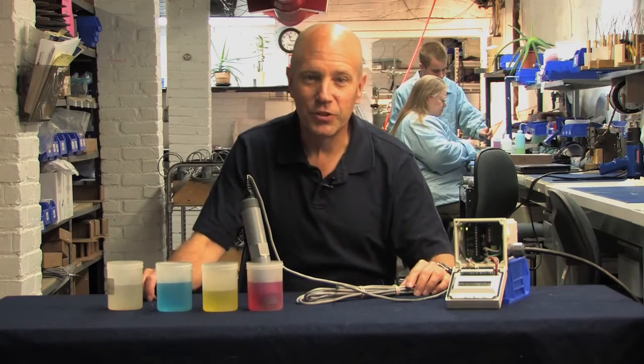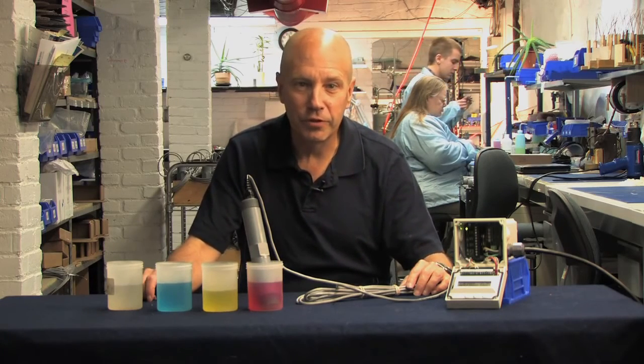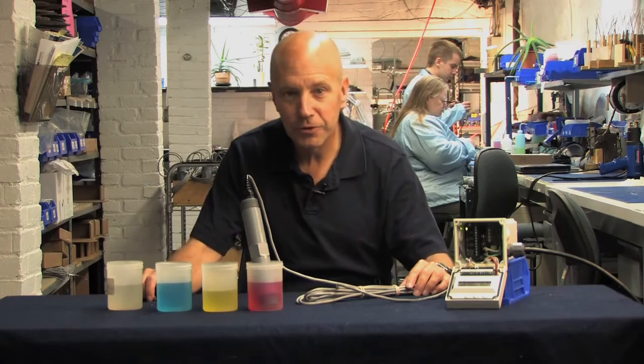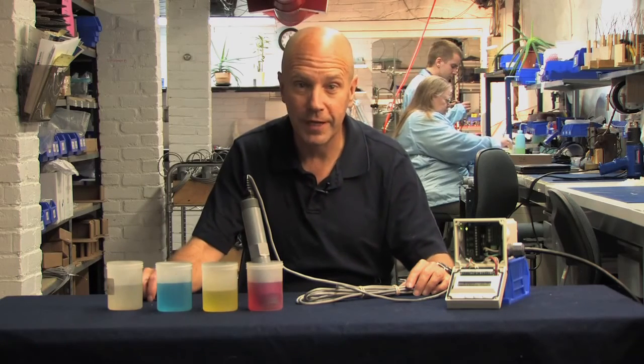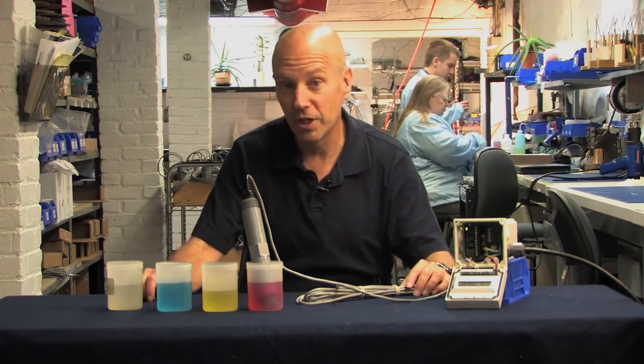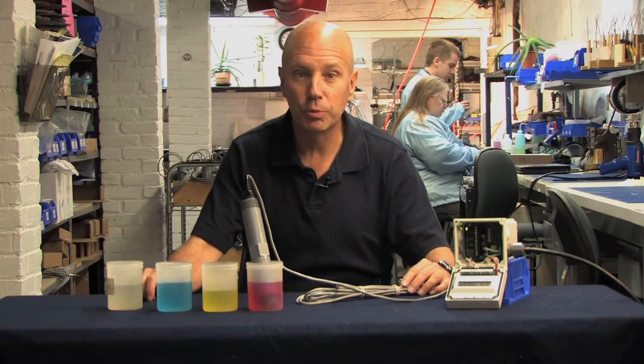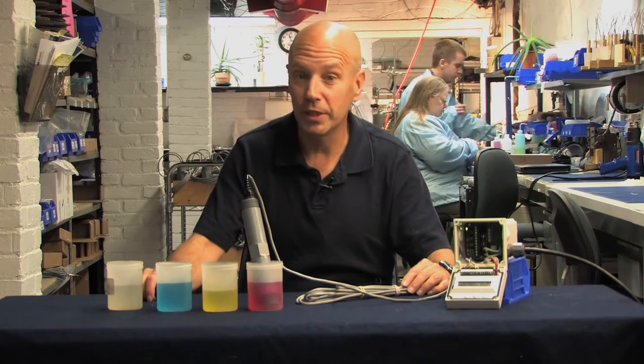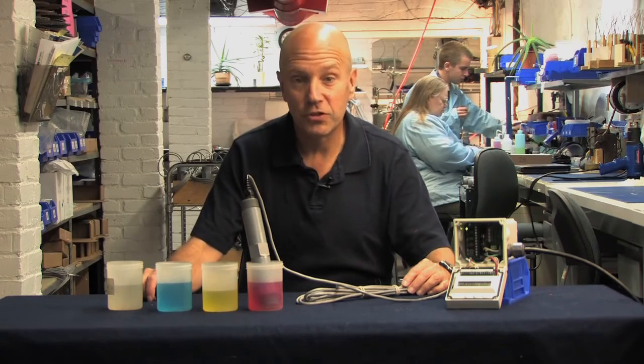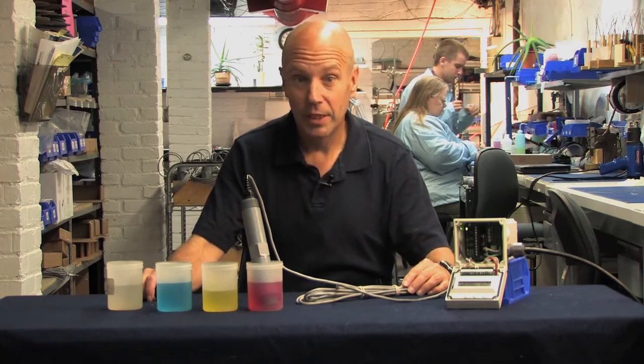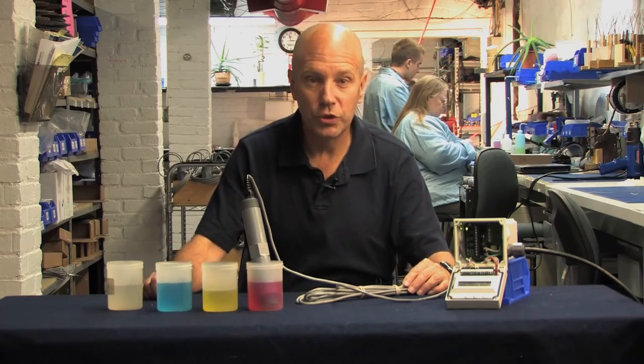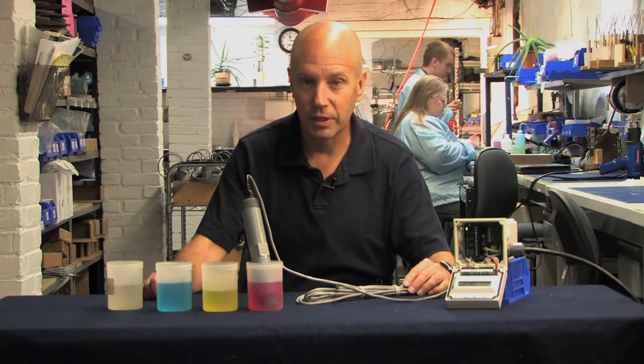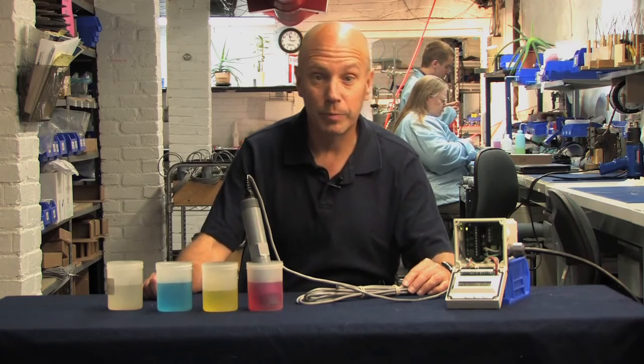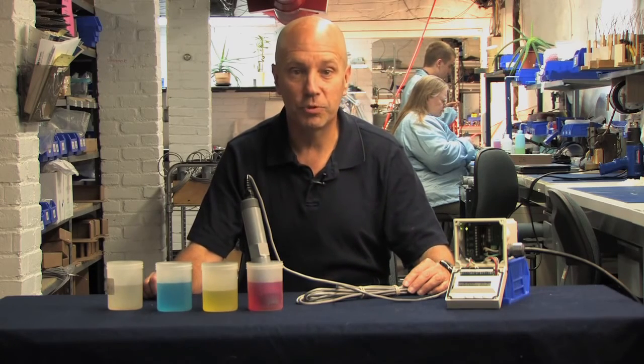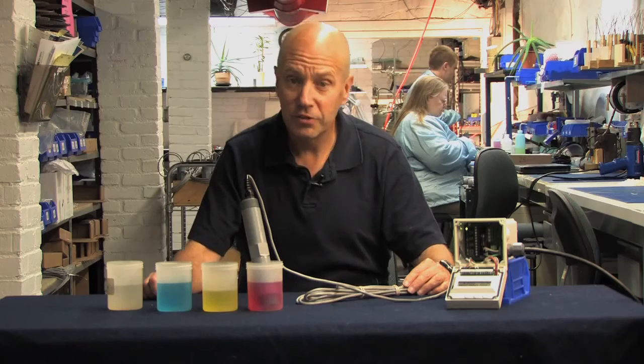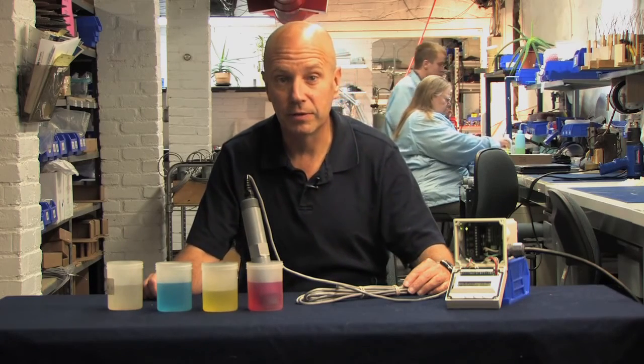Now, about that efficiency rating, we'll delve into the meaning of this number in the next video. But for now, suffice it to say that we don't let a probe leave the factory with an efficiency rating less than 90%. Your application of the probe will deliver accuracy to within 0.1 pH units as long as its efficiency is greater than 50%. However, there is no reason why you should accept performance of less than 80%. When you do get an efficiency of 80% or less, it's time to change out the reference pH 7 buffer solution. That's easy to do, and we'll cover that in the next video.